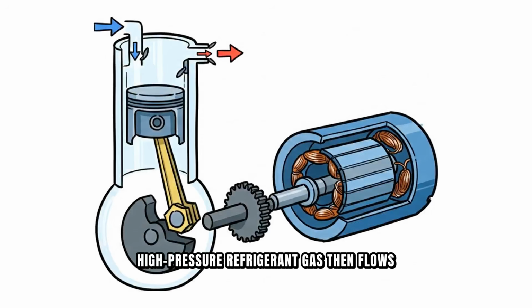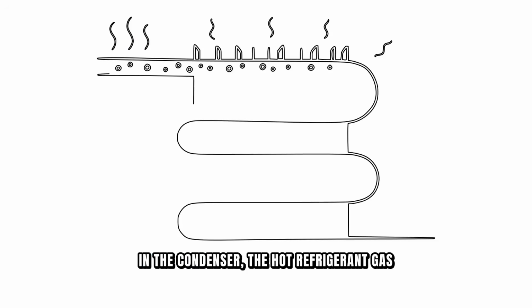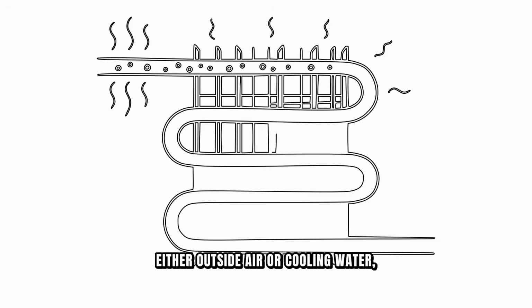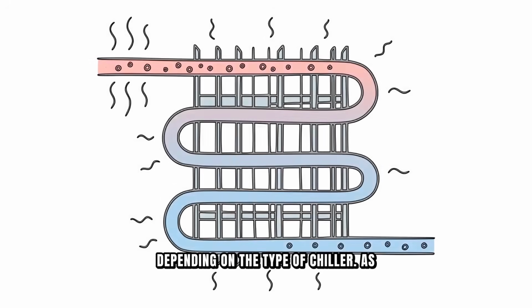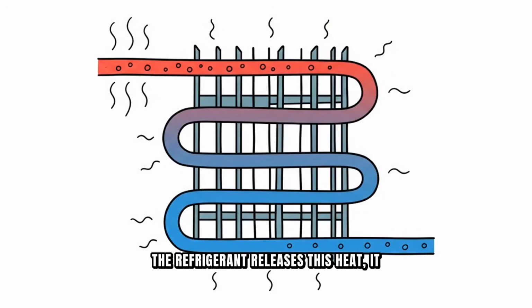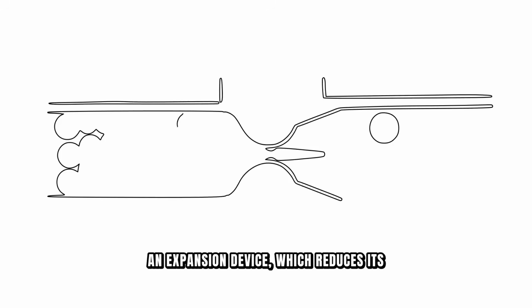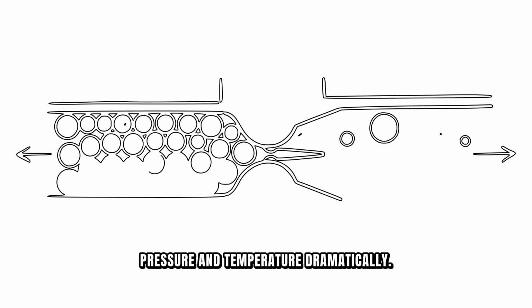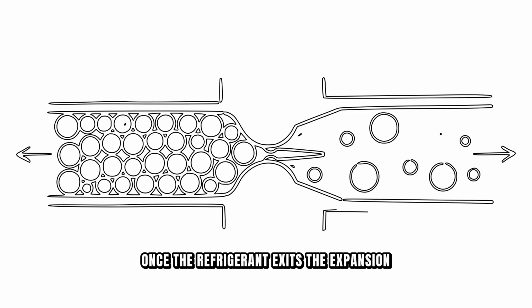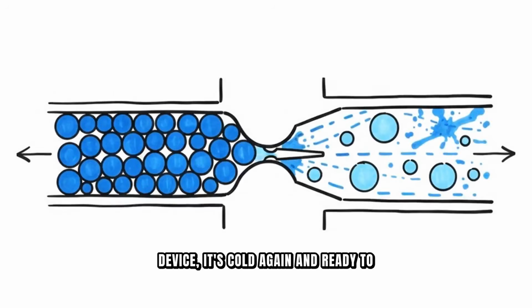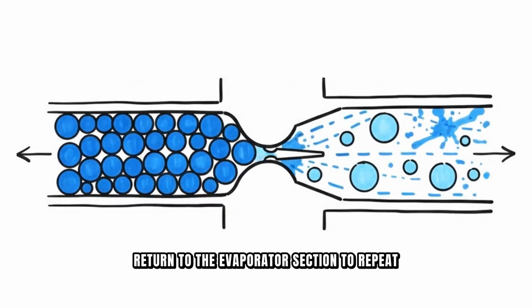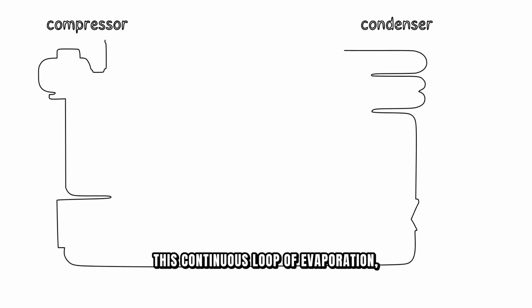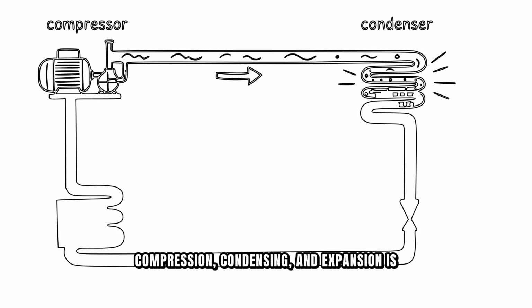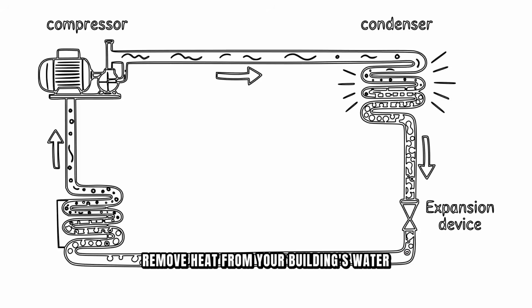The hot, high-pressure refrigerant gas then flows into the condenser section. In the condenser, the hot refrigerant gas releases the heat it's been carrying to either outside air or cooling water, depending on the type of chiller. As the refrigerant releases this heat, it cools down and condenses back into a liquid state. This liquid refrigerant then flows through an expansion device, which reduces its pressure and temperature dramatically. Once the refrigerant exits the expansion device, it's cold again and ready to return to the evaporator section to repeat the entire cycle. This continuous loop of evaporation, compression, condensing, and expansion is what allows the chiller to continuously remove heat from your building's water system.